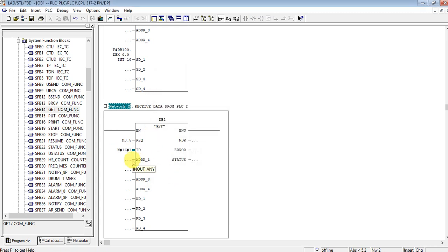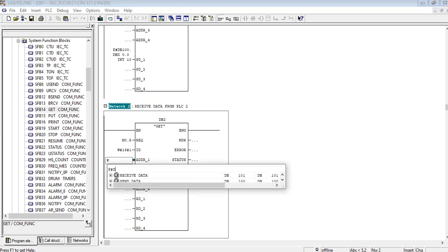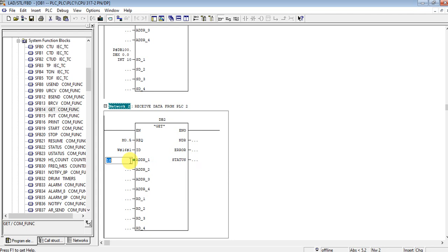Here also we have to check on this address which data is going to be received, which data is going to be fetched from the other PLC. We have to put the address of the other PLC's DB. That's 200. We are going to receive DB 200 from PLC 2, and we are going to receive 10 integers.